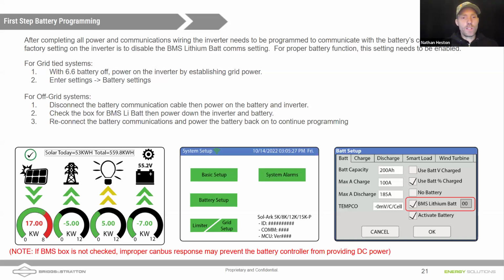And we're going to want to go into the settings. That's the gear icon in the top right. We'll go into battery setup. And once you get into battery setup under the BAT tab, there's a box that I've highlighted in red on the bottom right-hand corner. It says BMS lithium battery, and that tells the Sol-Ark, hey, start communicating on the CAN bus channel. And once we've got that box checked, we click OK to save. So remember, when you're programming a Sol-Ark, nothing gets saved unless you click the OK button. So click OK to save that, and then we can power on the batteries. And I'll show you that in the next step.